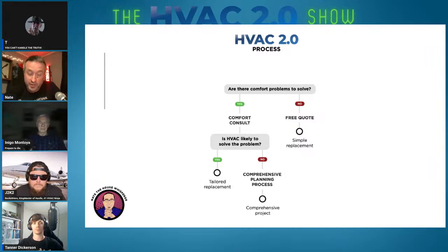But you need to be aggressive - you can't mess around. If it comes in at 32,000, don't put a 4-ton in. You might even need to do a 2.5 or a 2-ton, something like that. You're going to need to be aggressive to really make it work.